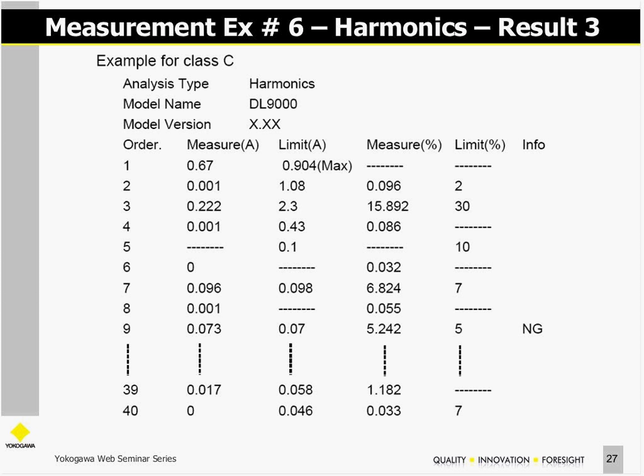Here's a tabular format. In this case, we failed a test on purpose to create a no-go, so it's another easy test. It shows the measurement of each order harmonic, the limit of each order harmonic, and your actual measurement in percent. In this case, I have a limit of 0.07 on the ninth harmonic, and I have a measurement of 0.073. So I exceeded the limit with a measurement of about 5% over - 5% no go. That's a failed IEC 61000 harmonic test.